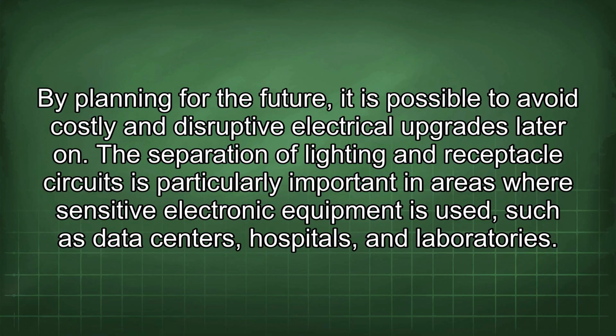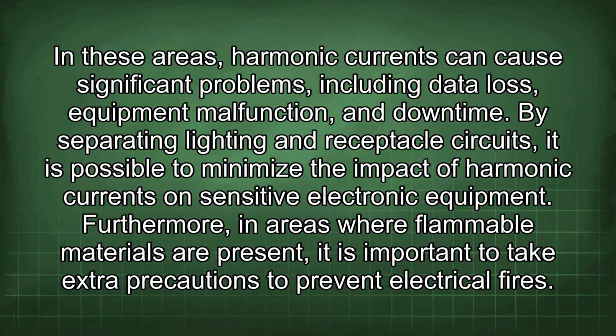The separation of lighting and receptacle circuits is particularly important in areas where sensitive electronic equipment is used, such as data centers, hospitals, and laboratories. In these areas, harmonic currents can cause significant problems, including data loss, equipment malfunction, and downtime. By separating lighting and receptacle circuits, it is possible to minimize the impact of harmonic currents on sensitive electronic equipment.